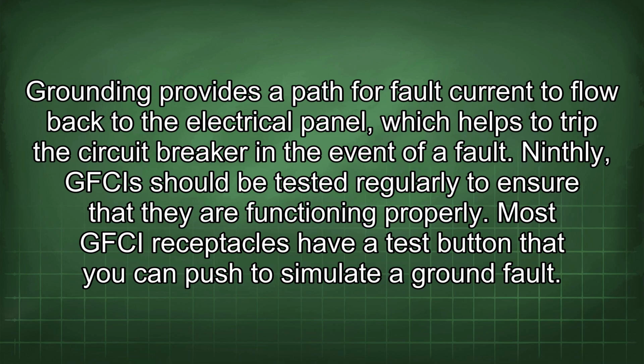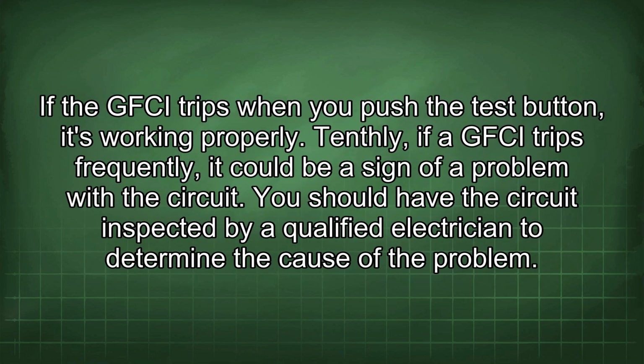Ninthly, GFCIs should be tested regularly to ensure that they are functioning properly. Most GFCI receptacles have a test button that you can push to simulate a ground fault. If the GFCI trips when you push the test button, it's working properly. Tenthly, if a GFCI trips frequently, it could be a sign of a problem with the circuit. You should have the circuit inspected by a qualified electrician to determine the cause of the problem.